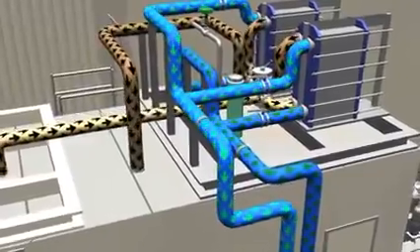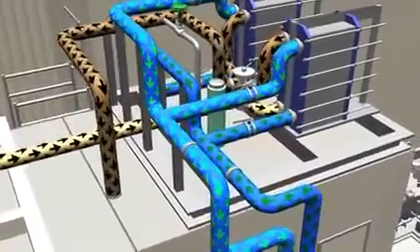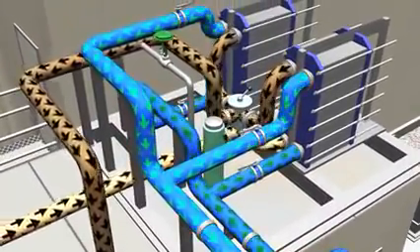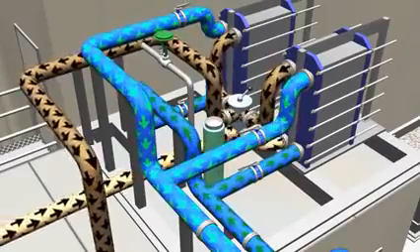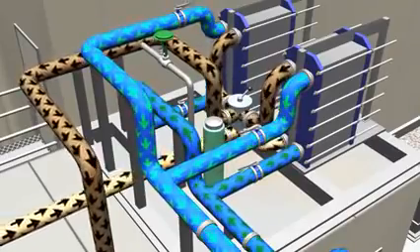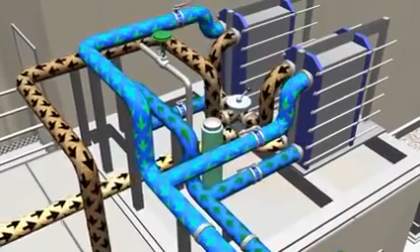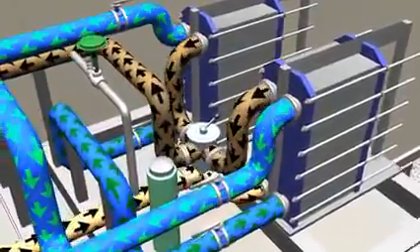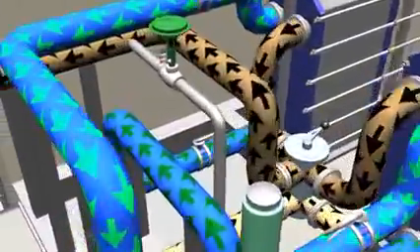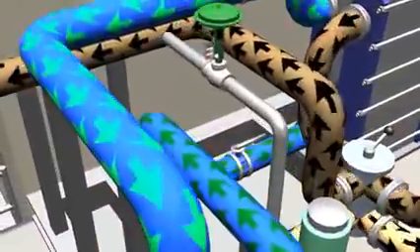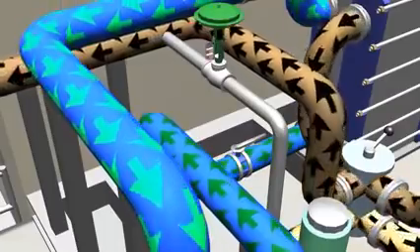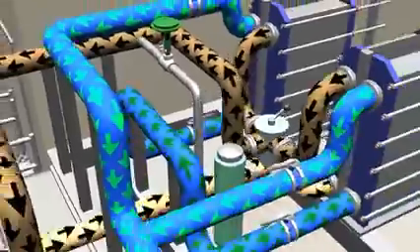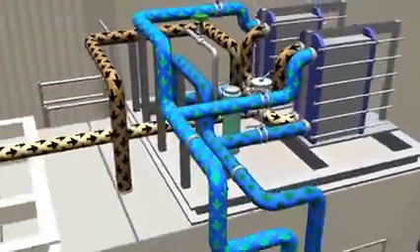Two 100% capacity lubricating oil coolers are mounted on the roof of the mechanical package. The coolers are of a plate type construction using closed cycle cooling water for heat exchange. A temperature regulating control valve maintains the lube oil at the desired operating temperature.